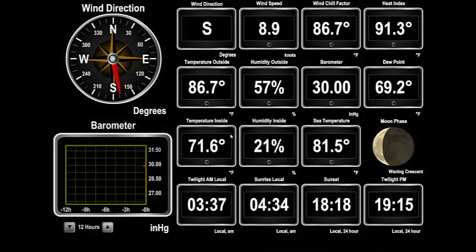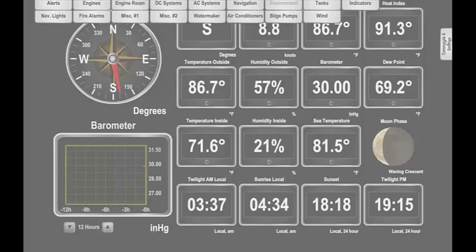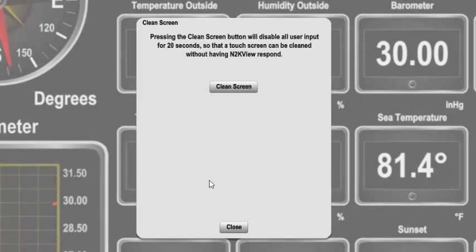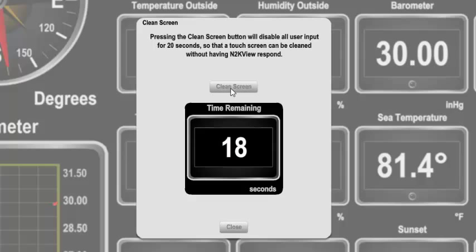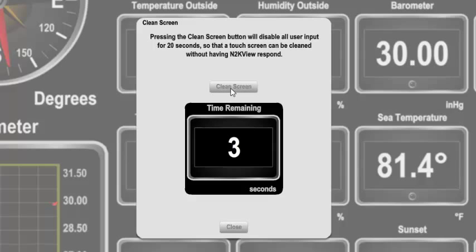Another useful feature is the Clean Screen function. If you want to clean a touch screen, you have to touch it to clean it. If you happen to touch a switch while cleaning it, you could do something inadvertently to the vessel. Pressing the Clean Screen button will give you 20 seconds of safety. You first get some instructions on what will happen, and when you press Clean Screen, you get a countdown of the time you have left. During this time, all user input from the mouse, keyboard, and touchscreen is disabled. N2K View continues to operate in the background and alerts continue to be monitored. When the count reaches the end, it returns to the normal operating mode.